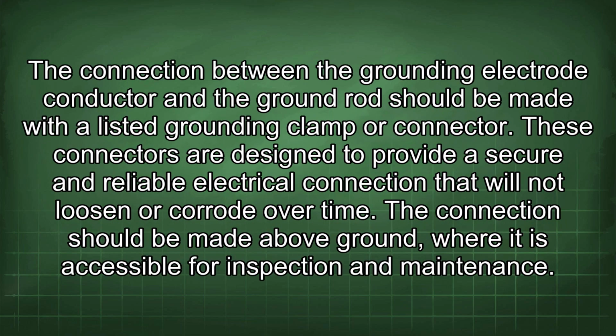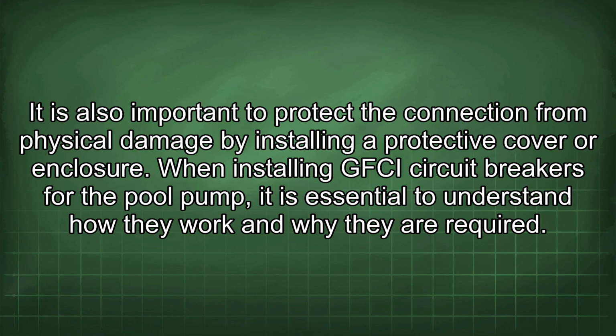It is important to use a conductor that is large enough to safely carry fault current back to the source. The connection between the grounding electrode conductor and the ground rod should be made with a listed grounding clamp or connector. These connectors are designed to provide a secure and reliable electrical connection that will not loosen or corrode over time. The connection should be made above ground, where it is accessible for inspection and maintenance. It is also important to protect the connection from physical damage by installing a protective cover or enclosure.